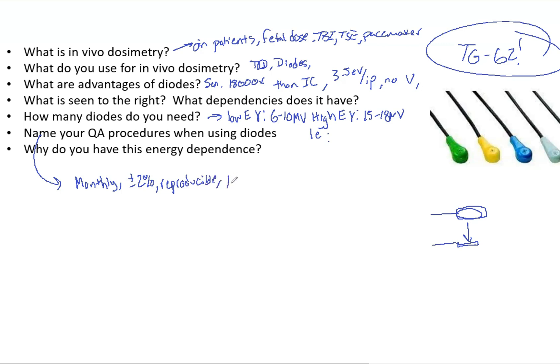You want that to be plus or minus 2% for your QA. You want your results to be reproducible. You want the leakage, because that's important. You don't want leakage on your diodes. You want that to be less than 0.5%. You want the dose rate dependence less than 2%. And you also want them to be linear. So if you increase MUs as you irradiate the same diode, you see that there is a linear pattern. So essentially, your reading at 100 MUs should be half that of 200 MUs.